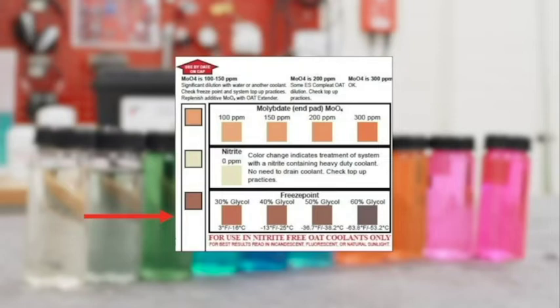Generally the glycol concentration should be 50%. If it's significantly lower than 50% the cooling system will need to be partly drained and fresh coolant added. If the results show coolant to be significantly over 50% glycol then the cooling system will need to be drained and topped up with demineralized water.